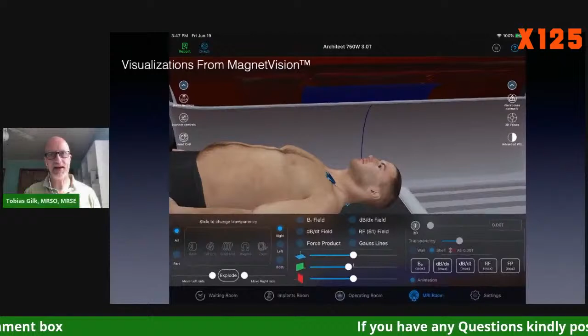So I mentioned a couple of times previously that we do have one option for collimation, for restriction of the physical spread. And that's if we use transmit-receive coils. So in the next animation, we're going to switch back and forth between the volume that receives RF radiation when we use the integral body coil built into the wall of the tube of the MRI versus using a transmit-receive head coil. Let's start that animation. We start out with the body coil, and we switch to the head coil.